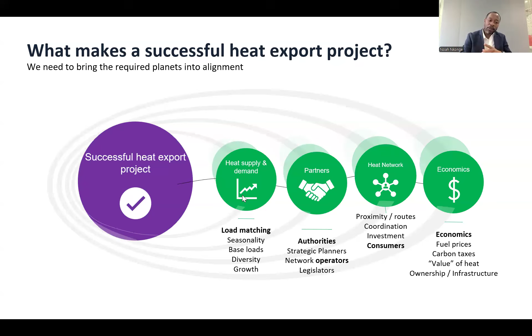As a rule of thumb, different studies have shown that generally we need about 1.5 gigawatt hours per kilometer per year of linear heat density for a project to be viable. That takes into account variables like the distance between the data center and the heat consumers, the heat density, etc. Those are some of the key ingredients of a successful project.